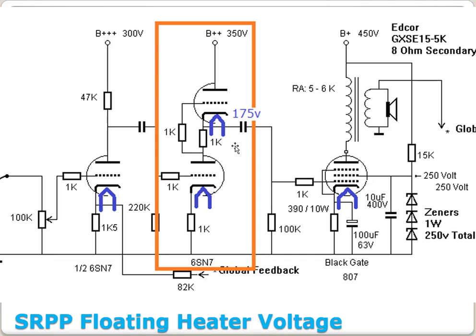But in this scenario, we've got to pay attention, because if we had not floated these heaters above ground to say 80 volts or so, and left them grounded like you typically would see in a heater setup, then you would have a delta between ground at this point and this cathode of 175 volts. Back to that schematic, it told us we had a 200 volt maximum, so I'm pushing it, and here's why.